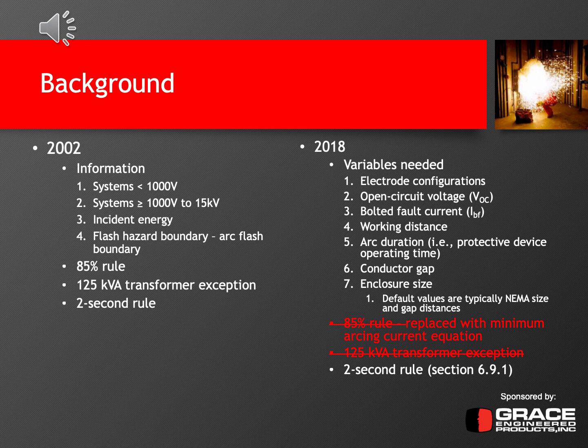In 2018, some of the variables that are needed are listed here, such as the electrode configuration, the open circuit voltage, bolted fault current, working distance, the arc duration, which is pretty much the protective device operating time plus some switching time if there's an actual switch that operates, the conductor gap, as well as enclosure size. And a lot of the enclosure sizes listed in the standard are the typical NEMA size enclosures and typical gap distances for the voltage ratings.